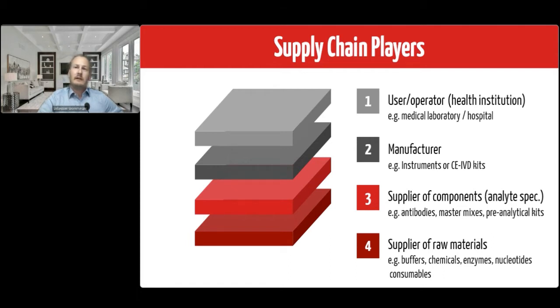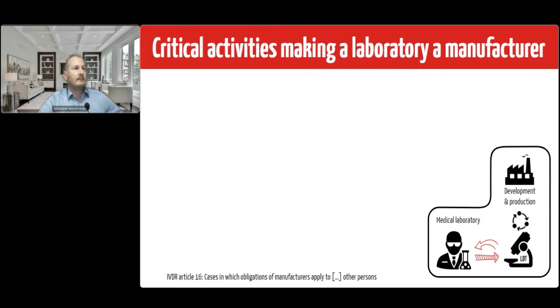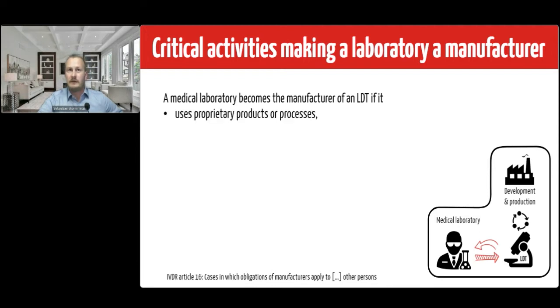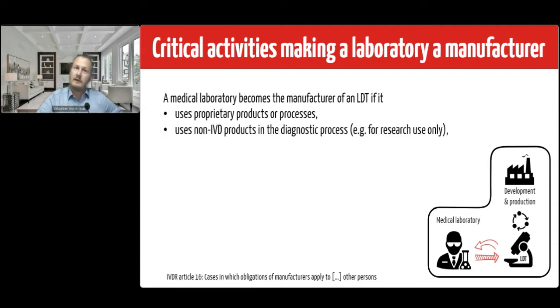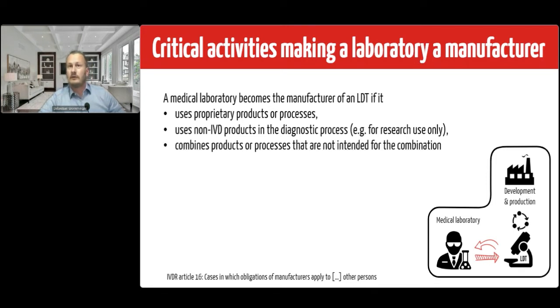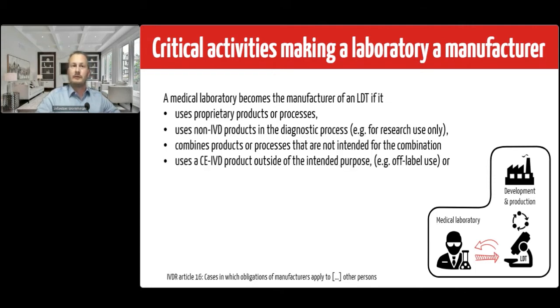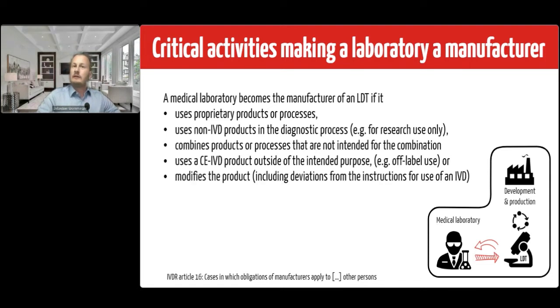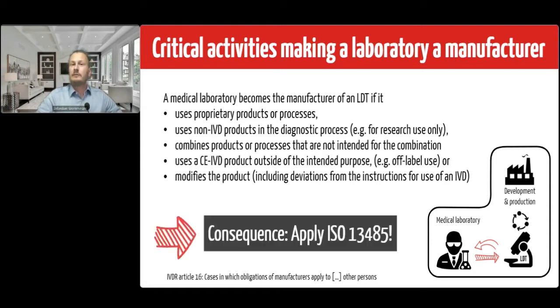consumables. Yeah, and let's look at this situation where laboratories take over some responsibility of manufacturers. So the critical activities making a laboratory a manufacturer are: if laboratories use proprietary products or processes, if they use non-IVD products in the diagnostic process, for instance, research use only products, if they combine products or processes that are not intended for the combination, or use CE-IVD products outside of the intended purpose, which we call off-label use, or if they modify the product, including deviations from the instructions for use of an IVD. So what is the consequence? The laboratories need to apply at least parts of the ISO 13485.